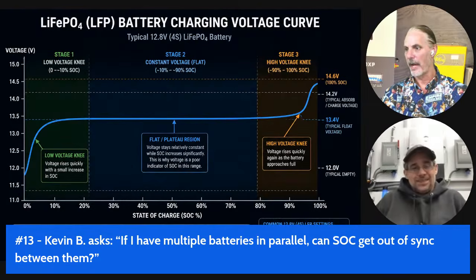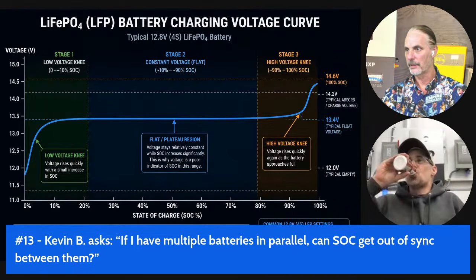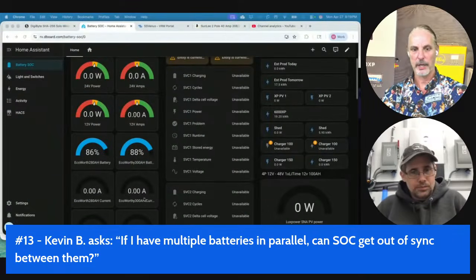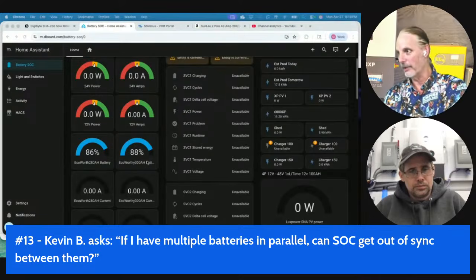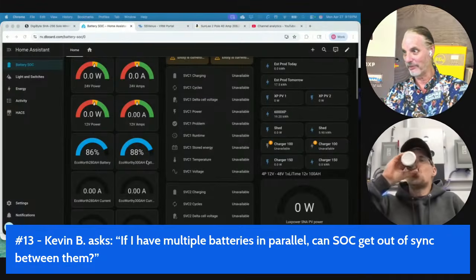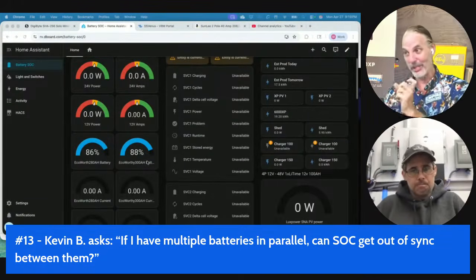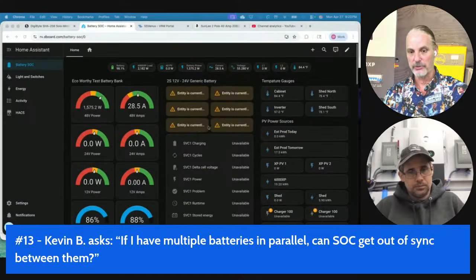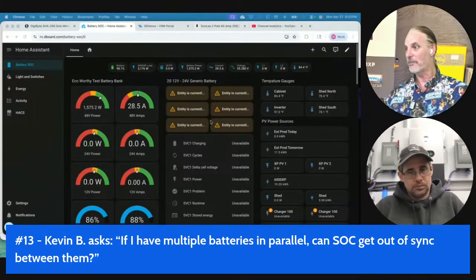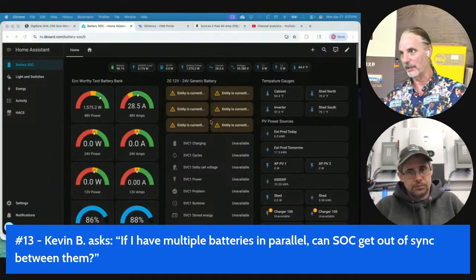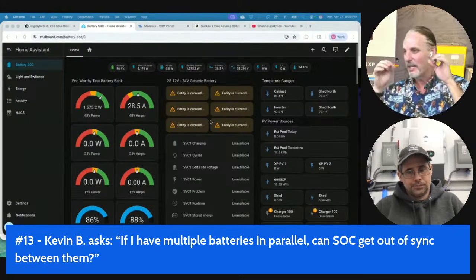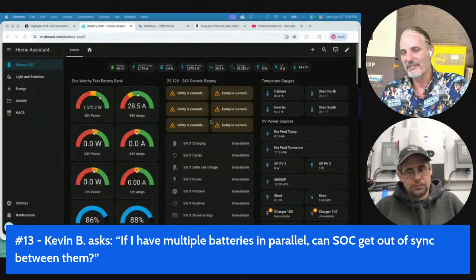I've got a bunch of batteries I test. Let me pull up this screen - I don't like the way it moves things around. You can see these two batteries here, 86 and 88: a 300 amp hour and a 280 amp hour. They run serially together - the 300 amp hour was only registering 280, so I put them together to test how close they'd actually run and find out what was going on. They actually stay really close. The only other ones that stayed this close were two Chinese batteries, the first two I ever ordered - they probably stay the closest I've seen. But yeah, batteries will get completely out of sync, running up and down even if they're the same size, bought at the same time, treated exactly the same, with perfectly sized cables. No two things are identical, and batteries are far from an exception to that rule.